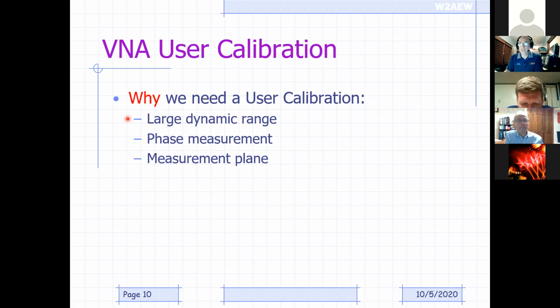So by doing a calibration, we establish something called a measurement plane. What we're effectively doing is calibrating out all of the other connections that we're making to our device, so we can make sure that when we measure phase, it's with respect to the right port of our DUT, for those instances where we care about measuring phase. Okay, but that's really one of the reasons.